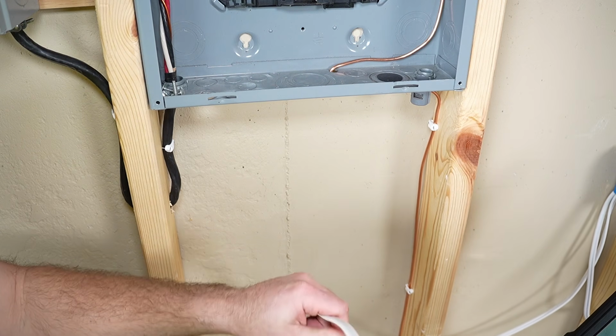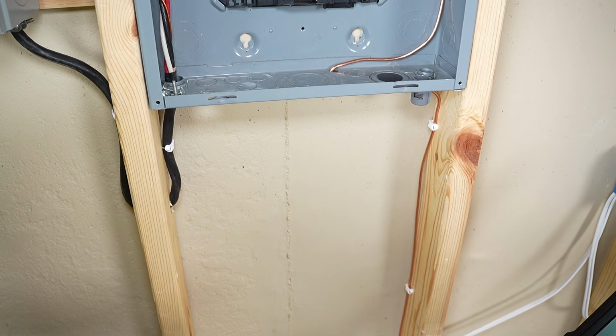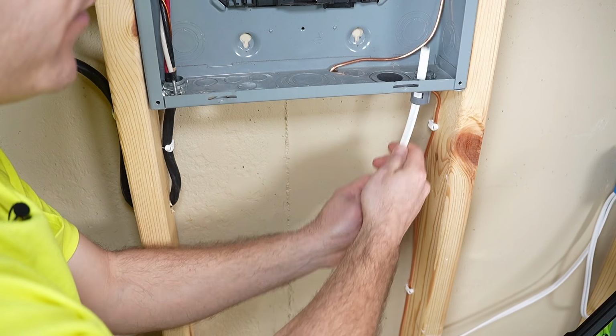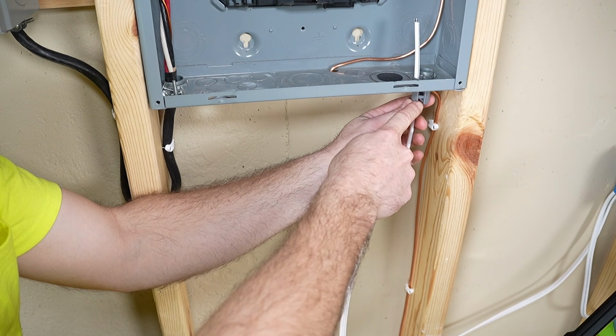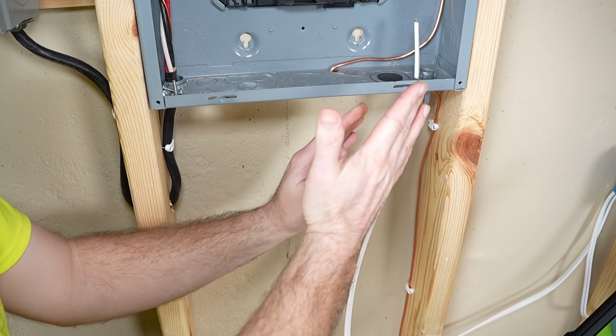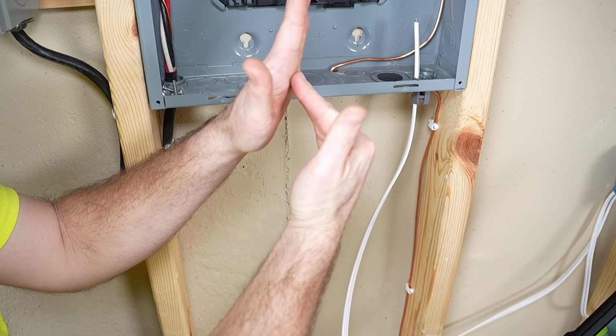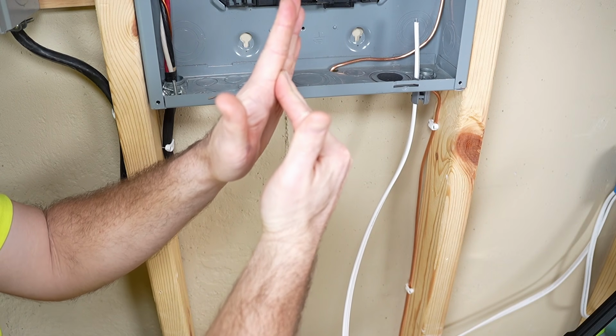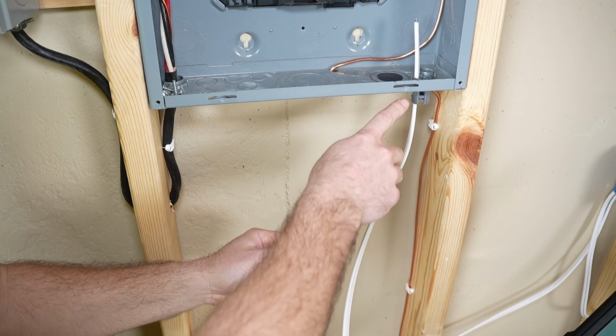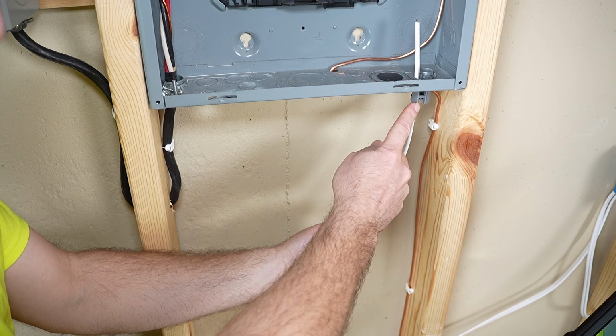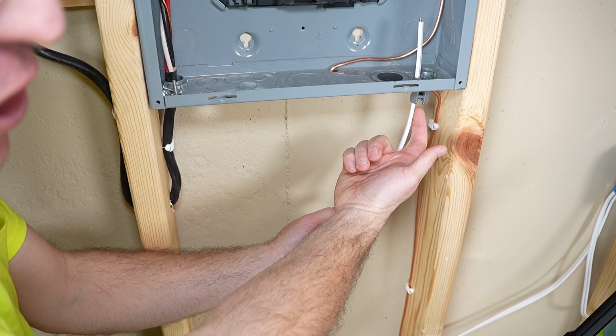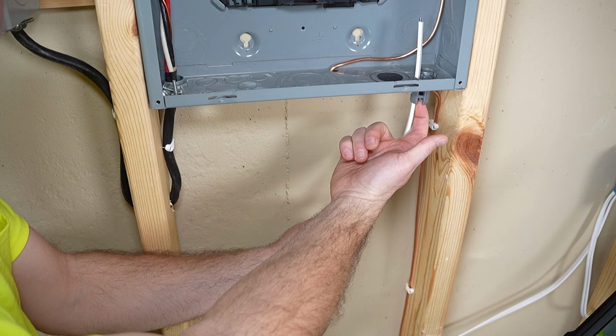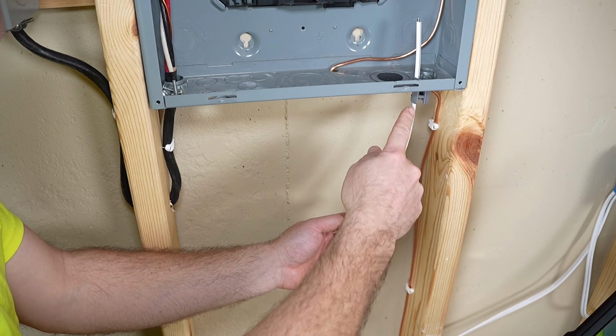So to get the wire in the electrical panel, we're gonna go ahead and grab this and just poke it up through this connector. This little plastic connector has a plastic wedge inside of it that actually allows the wire to push past it, but doesn't allow the wire to come out very easily. If you do need to remove a wire from one of these connectors, you can very gently push a screwdriver up from the bottom and bend that wedge out of the way.